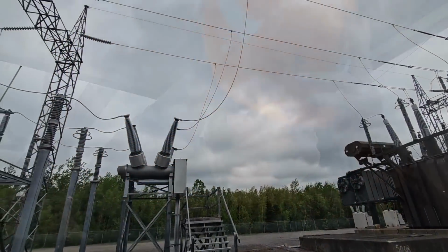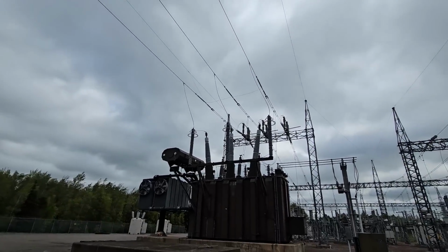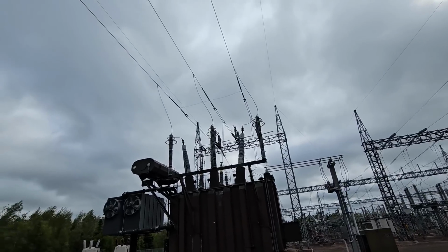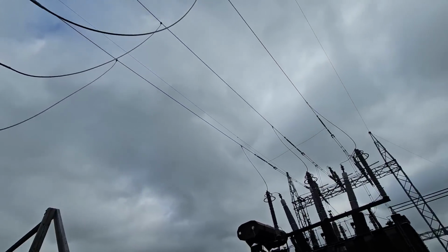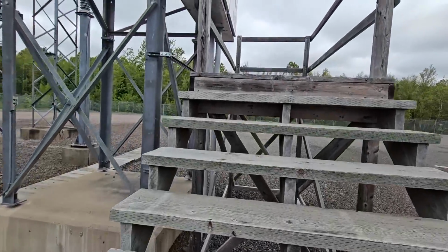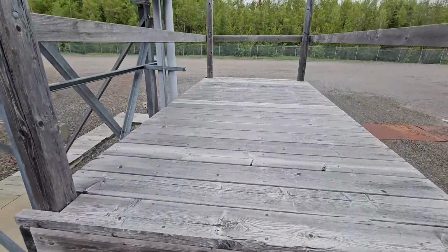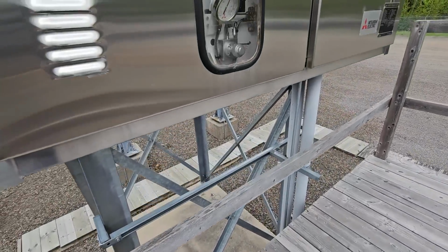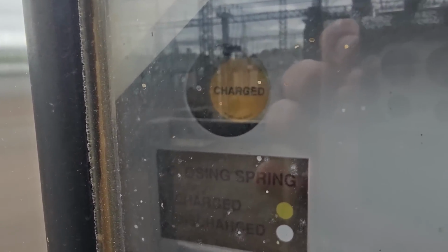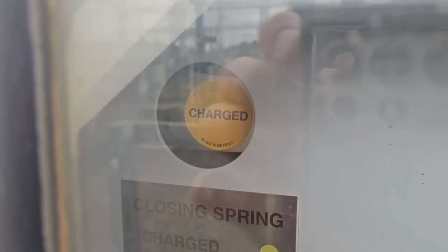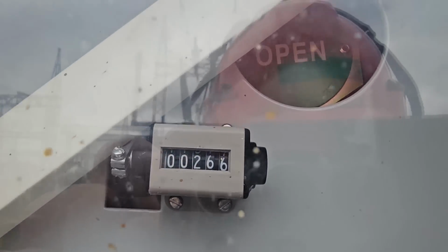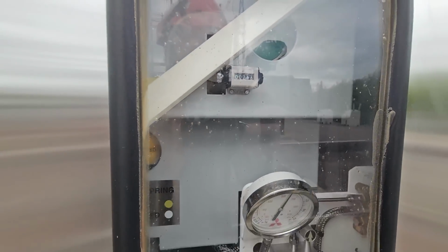But we will take a quick walk over and I'll show you guys how I do the check open on the air breaker. I don't know if you can hear the lines buzzing or not. That side is all still energized. Obviously I can't see what's going on inside this thing. We can see flags showing that the unit is charged, the closing spring, and internally device is open.